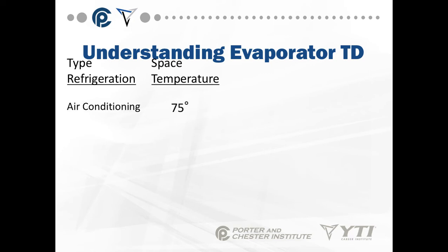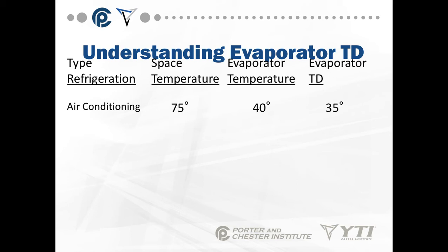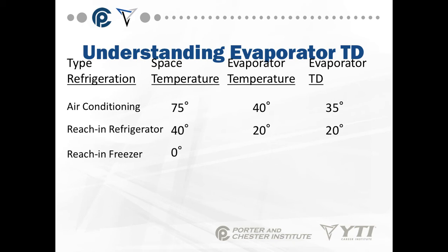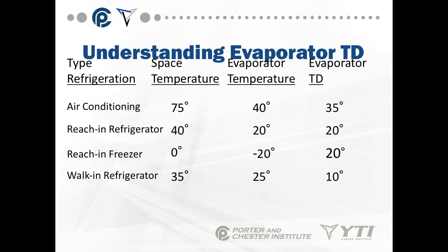To understand evaporator temperature difference, we need to know the type of refrigeration. Air conditioning: space temperature 75°F, evaporator temperature 40°F, temperature difference 35°F. Reach-in refrigeration: space temperature 40°F, evaporator temperature 20°F, temperature difference 20°F. Reach-in freezer: space temperature 0°F, evaporator temperature -20°F, temperature difference 20°F. Walk-in refrigerator: space temperature 35°F, evaporator temperature 25°F, temperature difference 10°F.